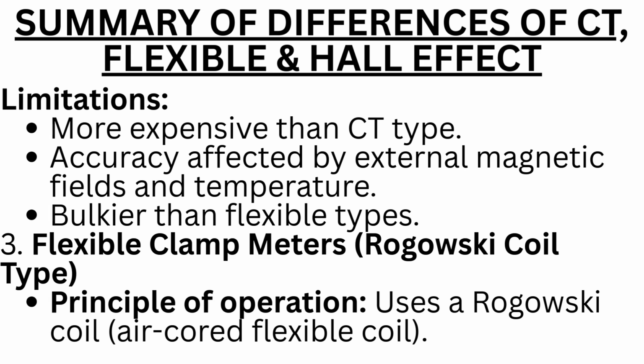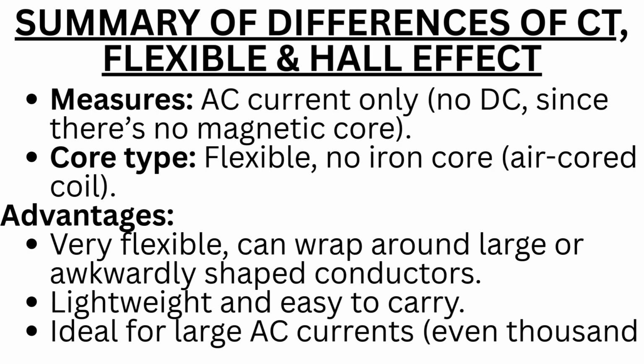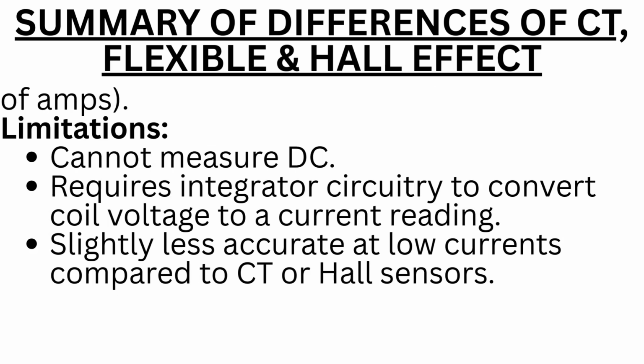3. Flexible clamp meters or Rogowski coil type. Principle of operation: uses a Rogowski coil or air-cored flexible coil. Measures AC current only, there's no DC, since there's no magnetic core. Core type: flexible, no iron core or air-cored coil. Advantages: very flexible, can wrap around large or awkwardly shaped conductors. Lightweight and easy to carry. Ideal for large AC currents, that is, even 1000s of amps. Limitations: cannot measure DC. Requires integrator circuitry to convert coil voltage to a current reading. Slightly less accurate at low currents compared to CT or Hall sensors.